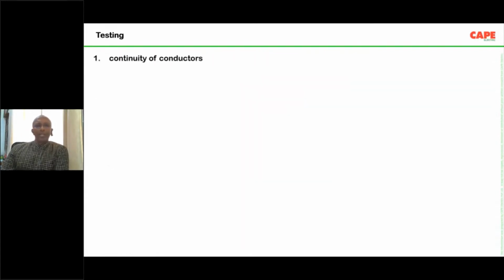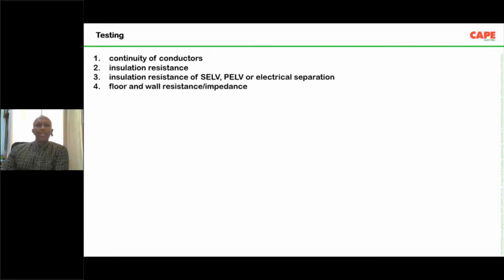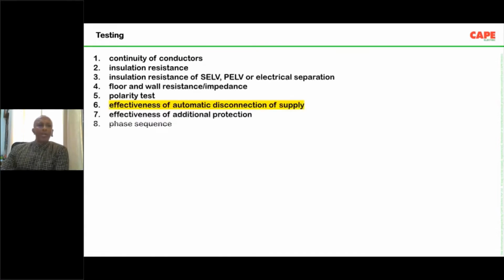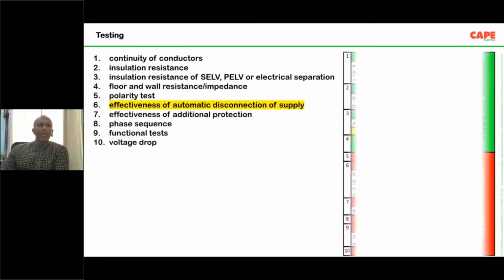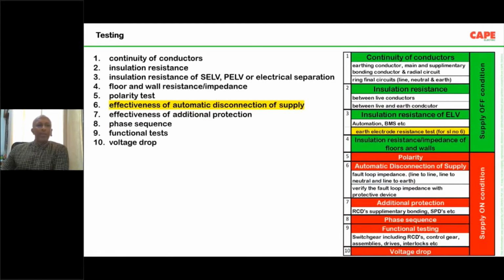Yes, the first test starts with continuity of conductors, then insulation resistance of SELV, PELV. These stand for extra low voltage systems. Then floor and wall resistance, polarity, effectiveness of automatic disconnection, and so on, starting with continuity of conductors and ending with voltage drop. There are about 10 different tests included in the standard.